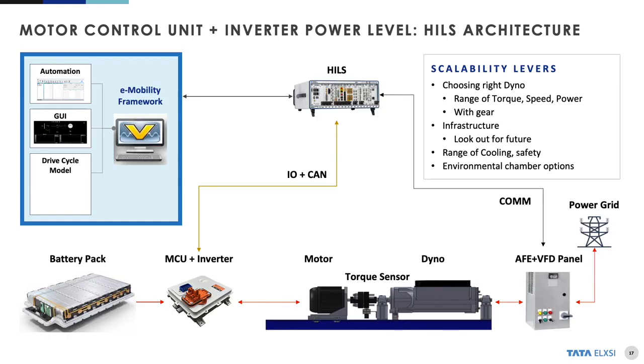We can also use a thermal chamber and chiller for validating temperature related functionalities of the MCU plus inverter, as well as the motor. So we have to keep in mind the capacity and ratings of the chiller and thermal chamber as well.